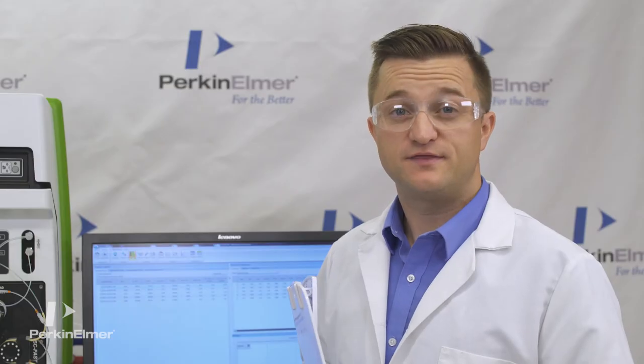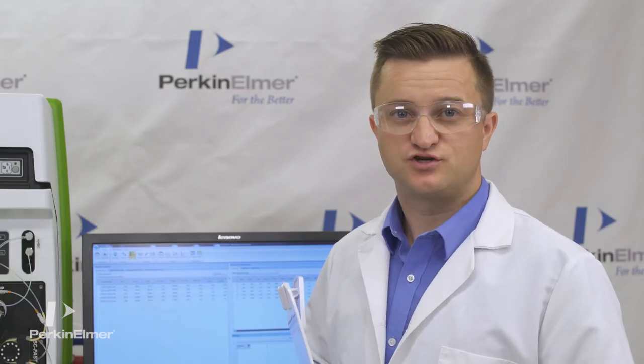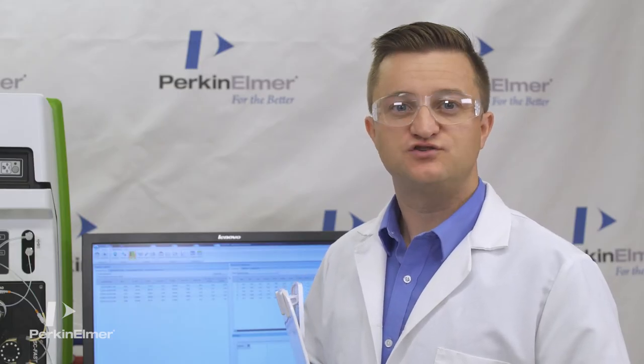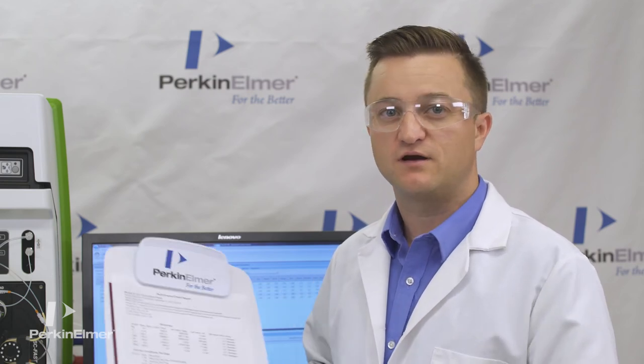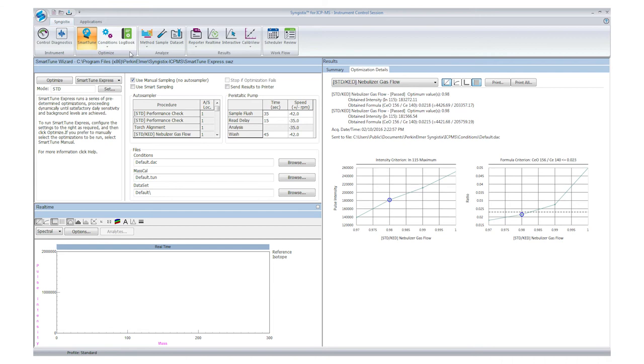Now that the optimizations are complete, Syngistix produces a hard copy performance check report, as I have here. In addition to providing an optional printout of the performance check data, Syngistix records the performance data into its internal logbook.